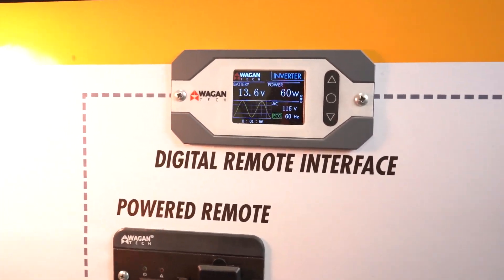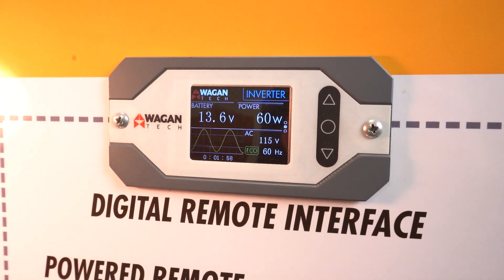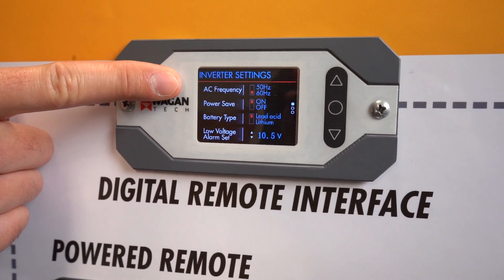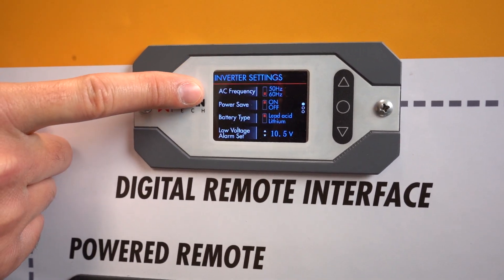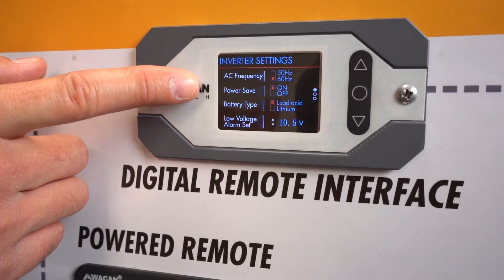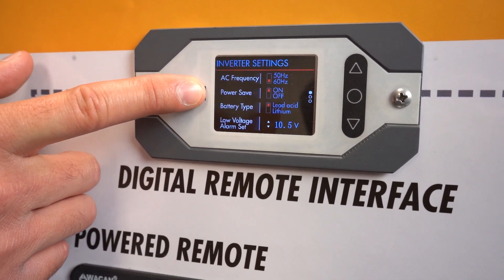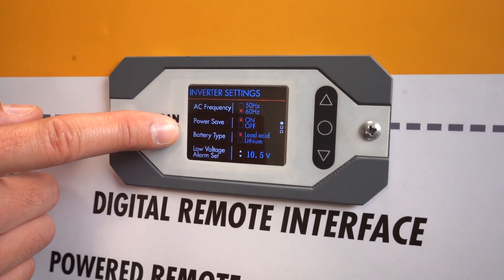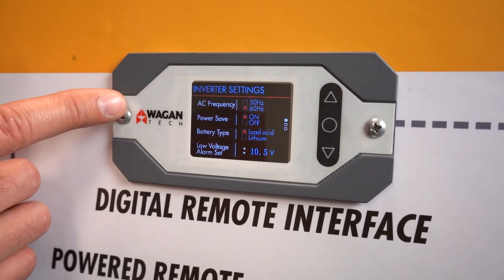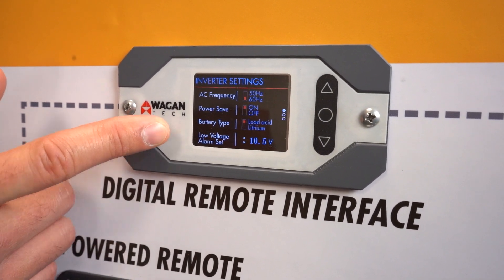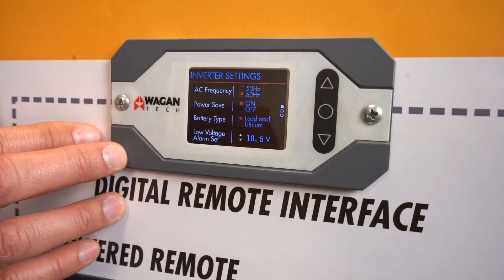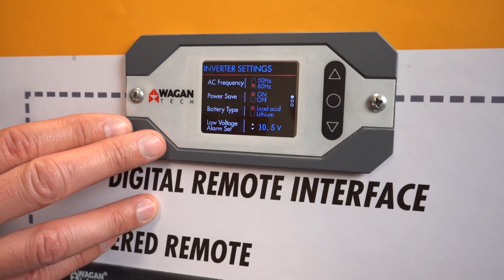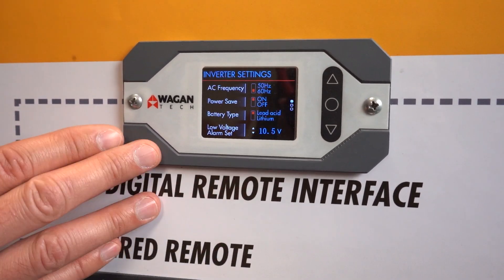Now we are going to take a look at the options mode for the digital remote interface. We will press the up arrow again. We can see the inverter has adjustable frequency settings — in the United States we use 60 Hertz. There is also a power save option which means the inverter goes into a low power standby mode when not in use, battery type selection for lead acid or lithium batteries, and low voltage alarm settings. For standard AGM, 10.5 volts is very common.